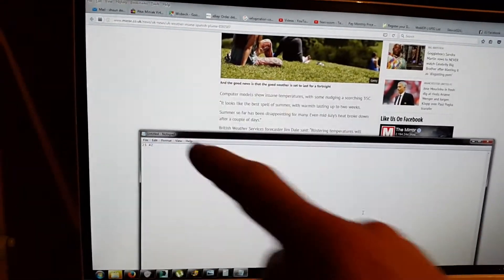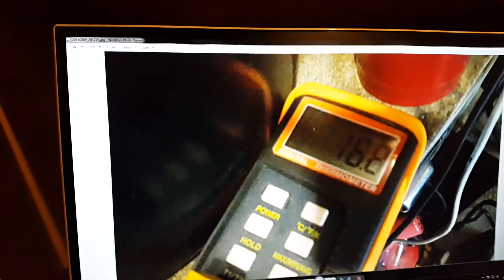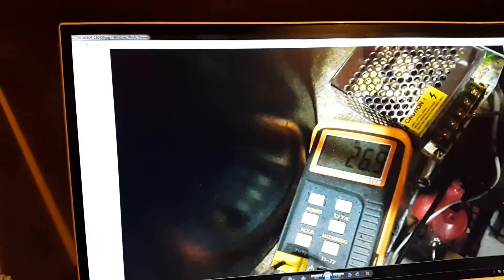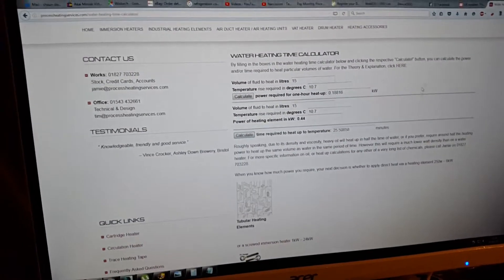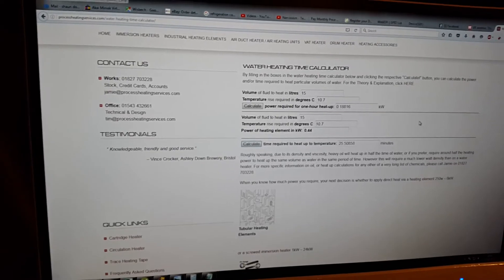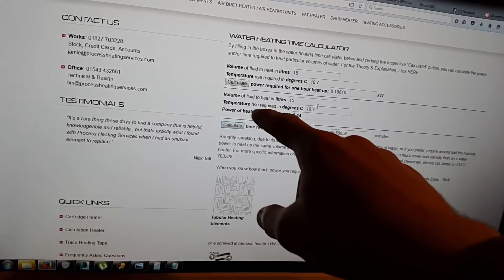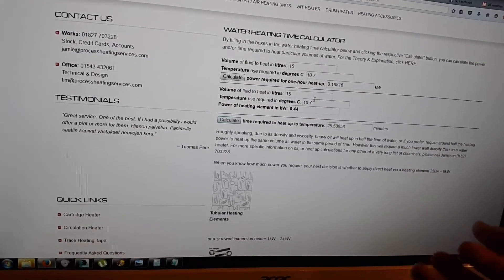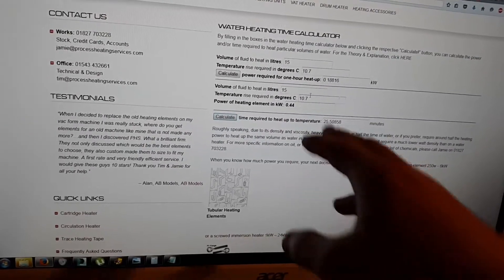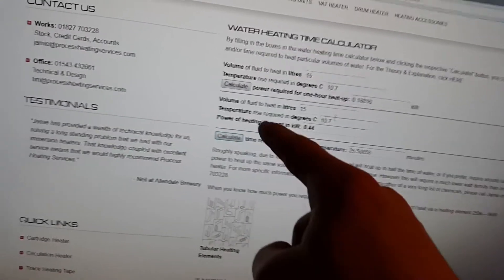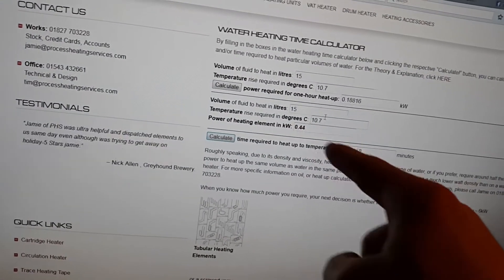OK, so I'm just going to add a bit on at the end here. I've done the power calculation. So I had a bucket of water earlier and it took 25 minutes and 42 seconds to raise the temperature of the water by 10.7 degrees celsius. It started at 16.2 degrees celsius and I rose the temperature up to 26.9. And after that I did the calculation on this process heating services calculator. So I had the volume of fluid to heat in litres, 15. Temperature rise required, so I just took away the end temperature away from the start temperature, or the start away from the end rather. I got 10.7. And I basically just played with the power of the heating element in kilowatt until I got as close to the time I recorded with a stopwatch.